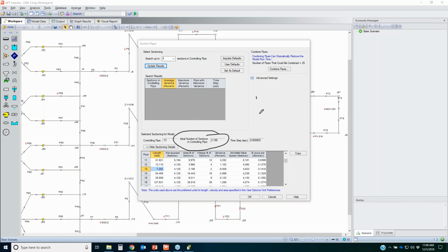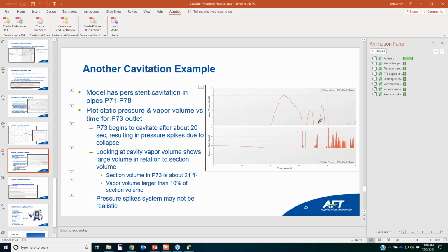So if you use 1 section, or maybe 2, or maybe 4, and you see the same types of trends and results in both cavitation models that you're seeing here, well, maybe these magnitudes might have a level of being realistic. But again, you're only going from 20 psia to 40 psia for the maximum values, so that may not be incredibly severe. Your piping system might be able to handle that. So that's how you can evaluate that in a bit more detail.